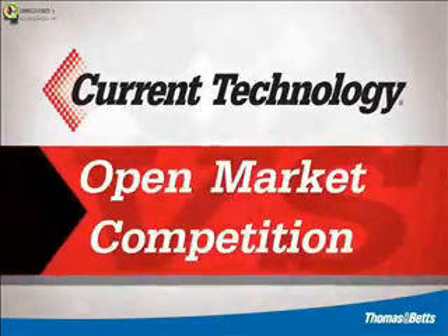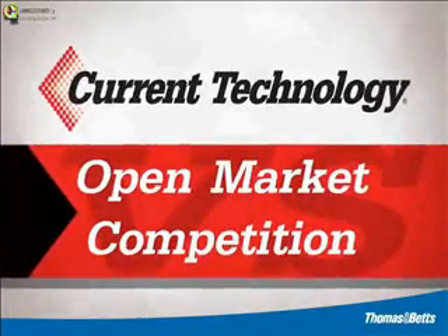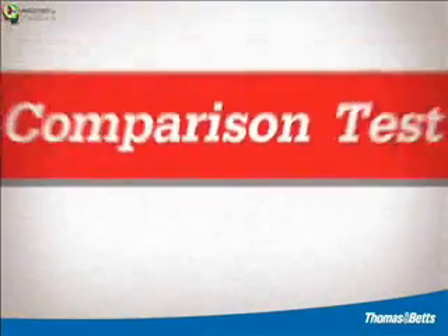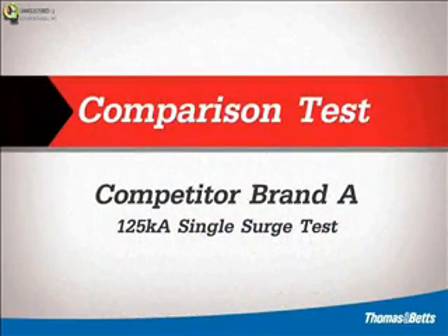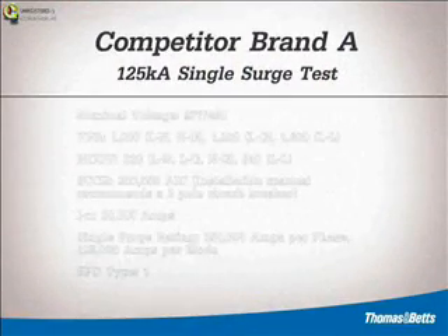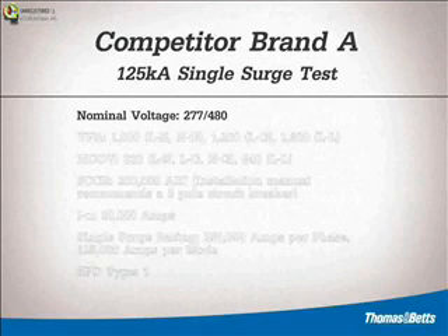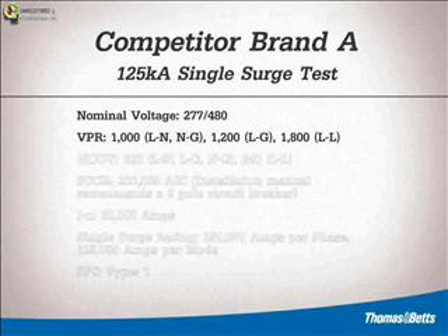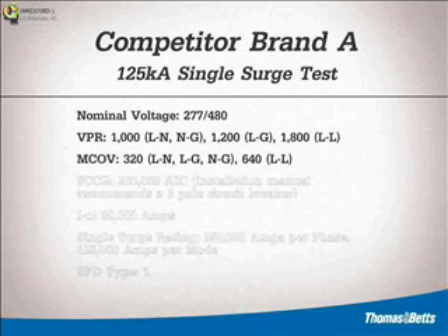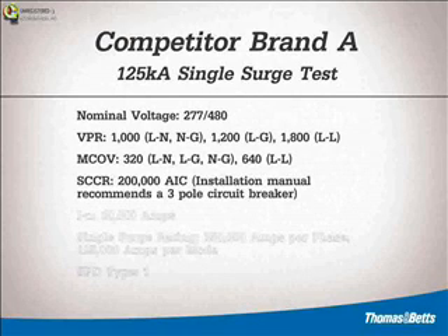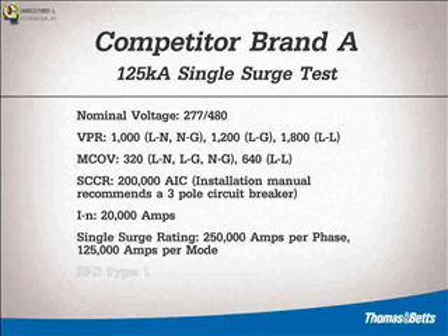It is for this reason that Thomas & Betts Power Solutions purchased several competitive surge protective devices on the open market and applied a single surge that matched the marketed single surge rating from the manufacturer. Brand A's marketed values include the nominal operating voltage, UL 1449 3rd edition voltage protective ratings per mode, maximum continuous operating voltages, short circuit current rating, nominal discharge surge current, single surge rating per phase and per mode, and SPD type as defined by UL 1449 3rd edition.